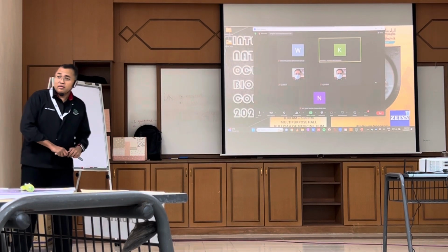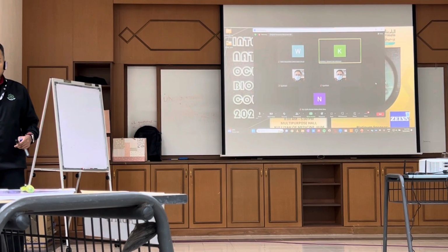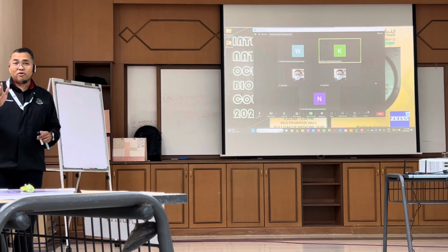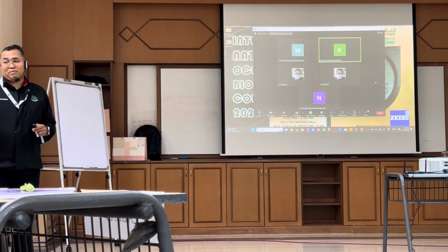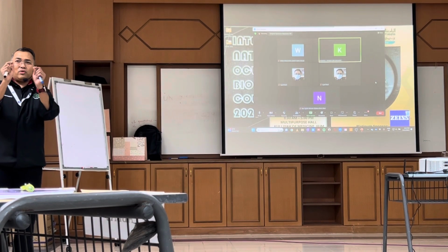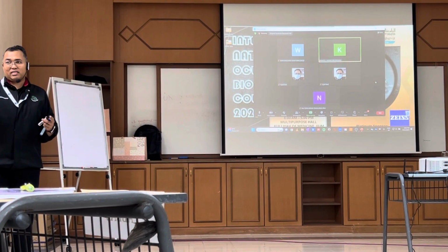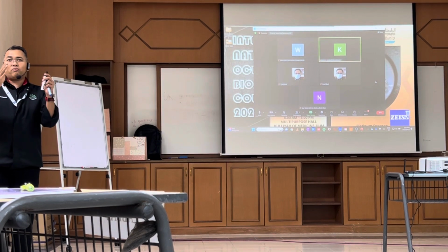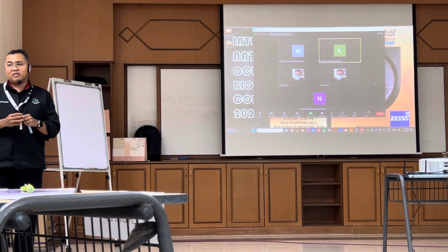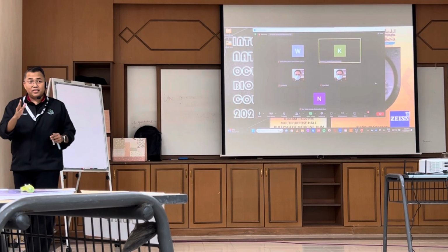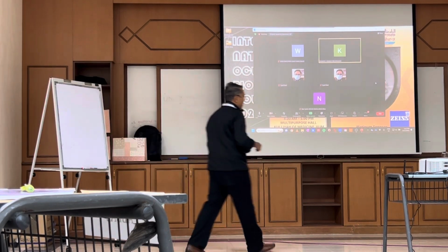Yes, no question. The A constant is a number. How to change the A constant? Okay, first and foremost, get the company involved, because once you get them involved, they have to recheck. And we know how to do it manually, because remember that you have the difference of 0.3, right? And usually they just play with that 0.3. Let's say it is 118.3 for optical, it becomes 118.0 for the ultrasound. Even though we know how to do it, you need to ask back to the company, get them involved. They usually are able to do that.